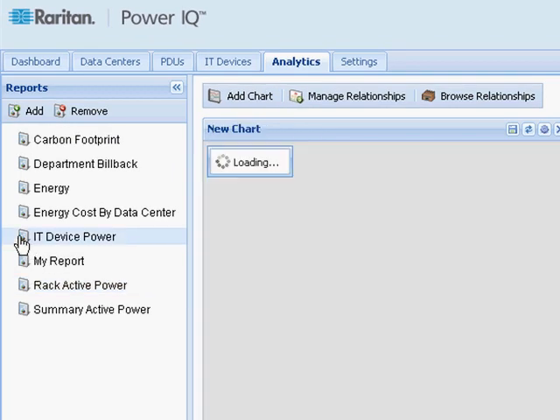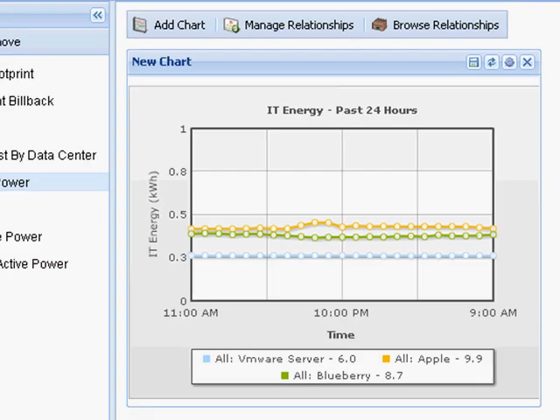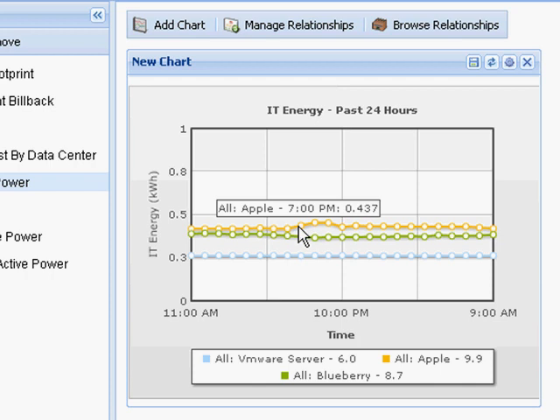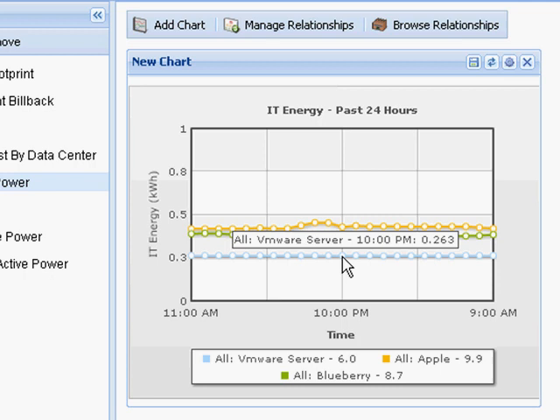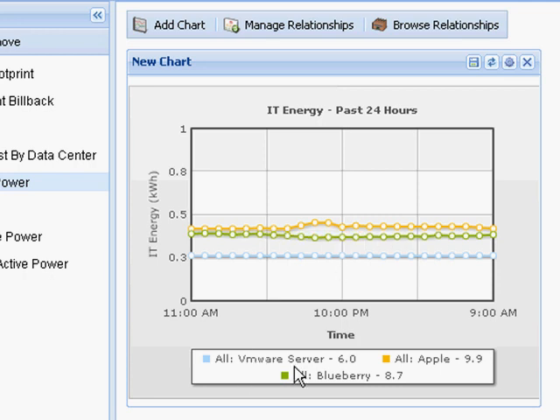For my canned reports, a big differentiation that Raritan provides is the ability to graph IT energy by individual device level or groups of IT devices. In this particular chart, I'm graphing IT energy for the past 24 hours in kilowatt hours, and I have my individual trend line for a server named Apple, another server named Blueberry, and a third server named my VMware server. The window here provides the cumulative total over the graphed period in kilowatt hours.